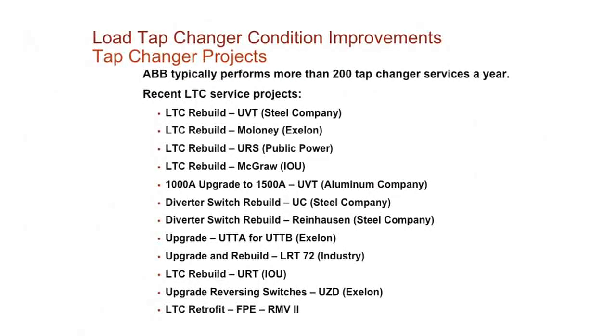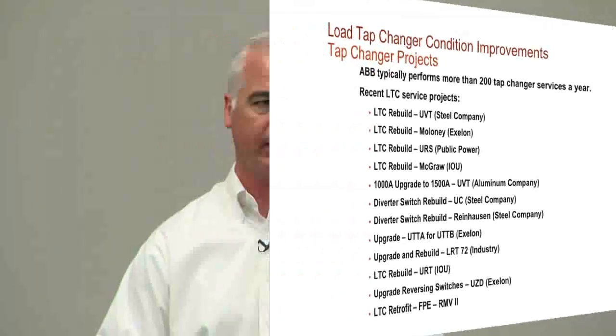Basically, we perform over 200 service maintenance on LTCs a year, whether that's retrofits, whether that's inspections, whether it's actually maintenance on LTCs. But you can see the list, basically some service projects that we've done recently. We do it for industrials, we do it for utilities. About any LTC out there, we have someone that can service the LTC, so it just depends on the end user, where they're located, depends on how long it takes to get someone there. These guys are normally booked quite frequently months ahead of schedule, so if you have LTC maintenance you're looking at, it's something you need to plan ahead on.